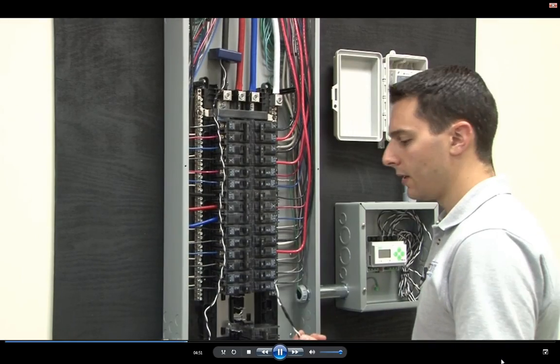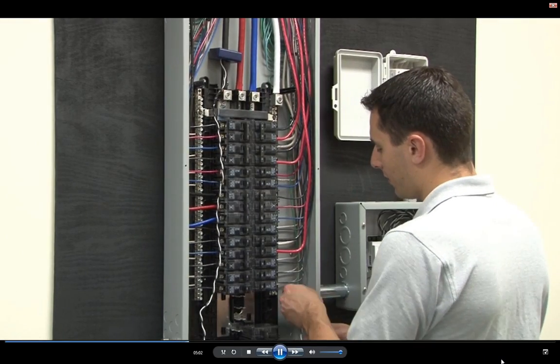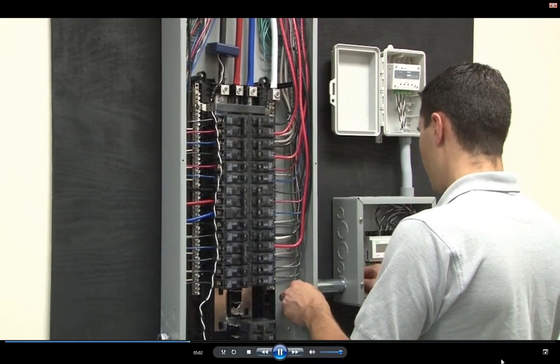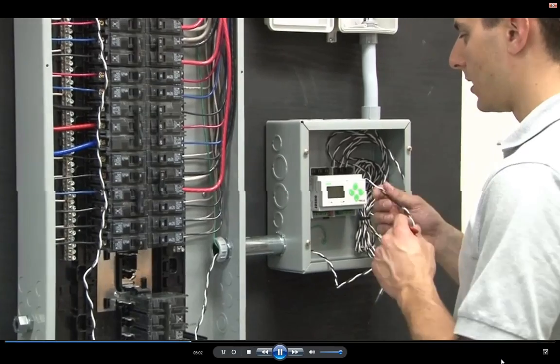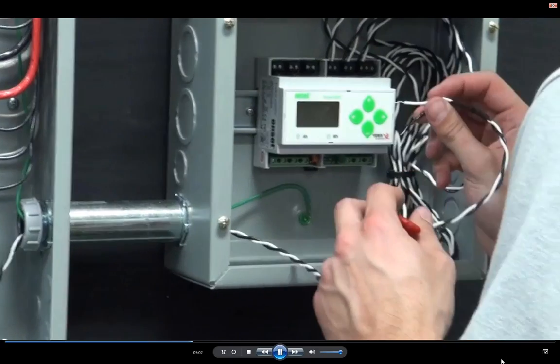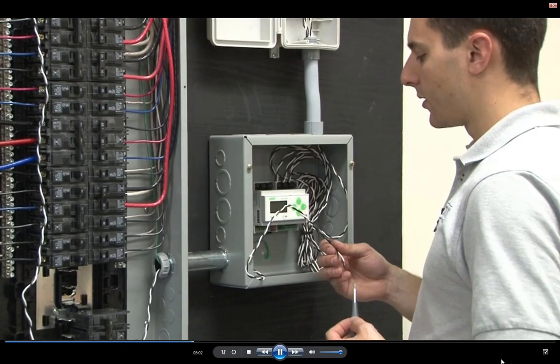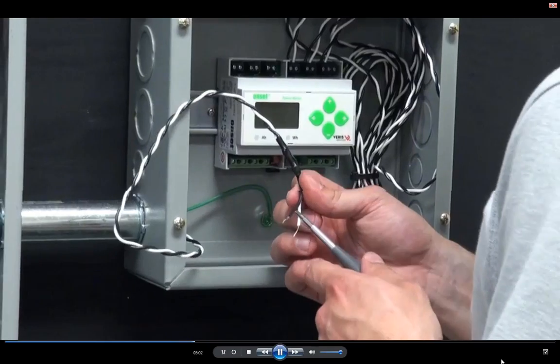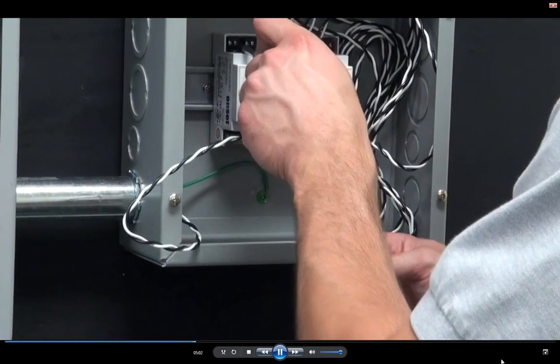And we run our CT conductor back through the 1-inch conduit to our E50B2 meter, to the phase A CT terminal. Because these CTs are directional, it's important that the white conductor connects to the positive terminal and the black conductor connects to the negative terminal.